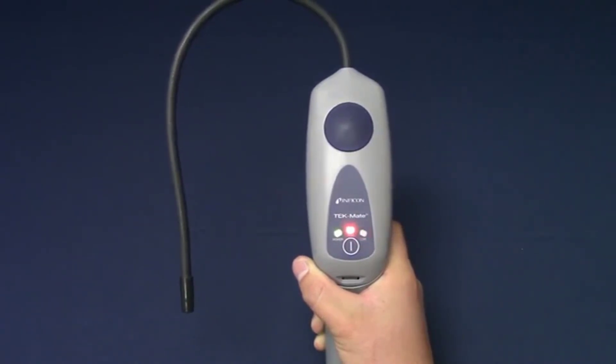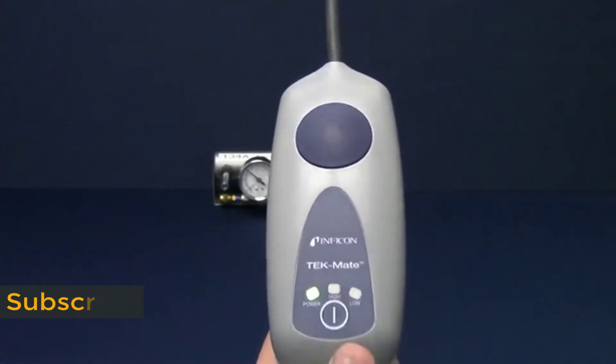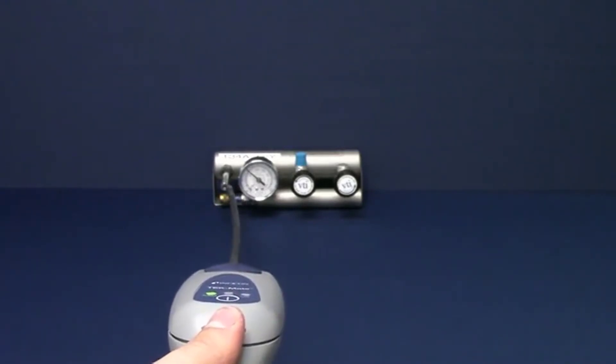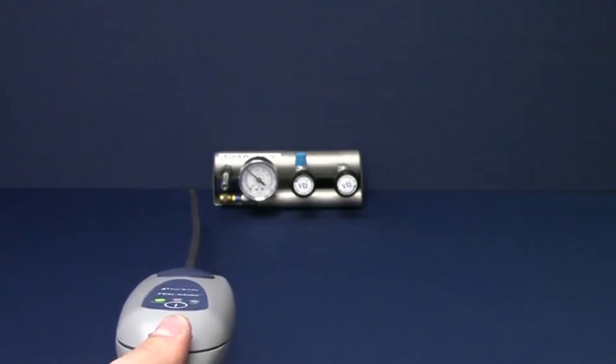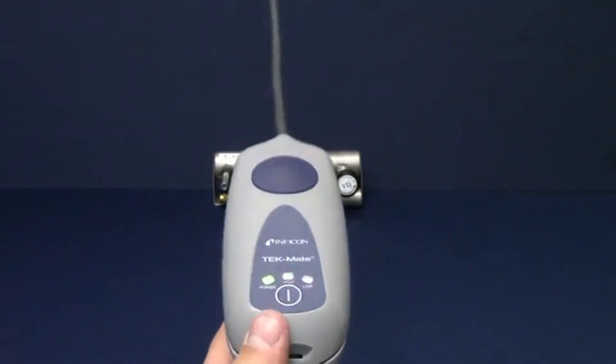TEK-Mate always starts in high sensitivity. This mode is useful for finding the general source of the leak. Begin by moving the probe slowly around the suspected leak. TEK-Mate will beep faster the closer it is to the leak until a continuous beep is heard. Move the probe away from the suspected leak for a few moments and repeat to verify the leak.